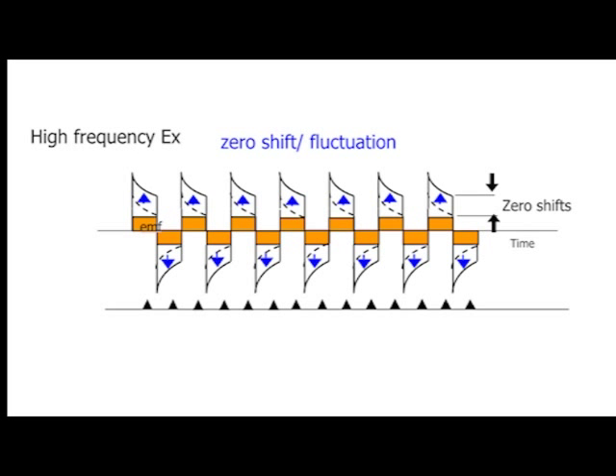On the other hand, in the high frequency excitation method, the excitation frequency is fast and the sampling rate is fast, so the induced noise does not have a chance to dissipate. In high frequency excitation methods, the zero point is more likely to be unstable.